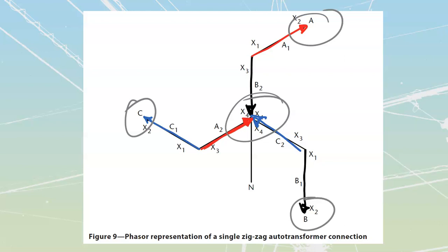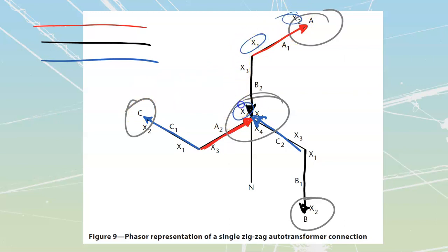If I've got a delta system, let's say I've got a delta bus over here, and I want to connect some single-phase loads, or I have some single-phase loads that sometimes do exist on there, just transient loads or something. What I'll do is place one of these across here. Now, you'll note that everything over here is X's. What they're showing you right now is that this is a zigzag filter right now, okay?